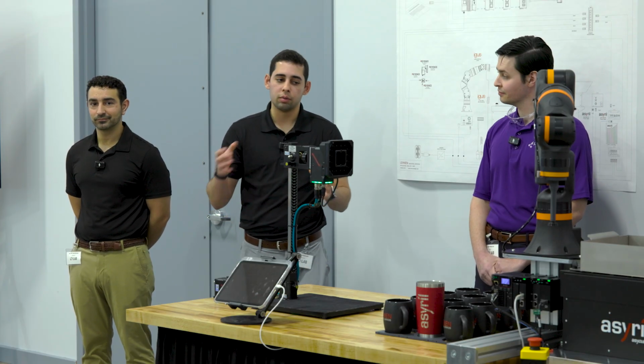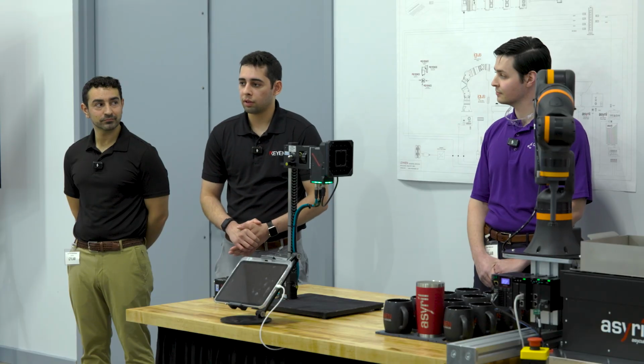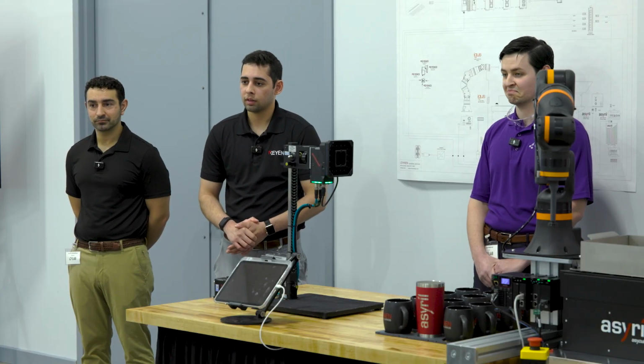Any questions on how you would utilize this system? Is there a limit to how many tags you can buffer? So you're recording like the last 10 minutes of video or something? Yep, it's 1,024 per PLC. Tags or bytes? Tags, 1,024 tags. Are you able to do it with the alarms, like say any alarm, or are you actually putting tags in and monitoring certain outputs or whatever?